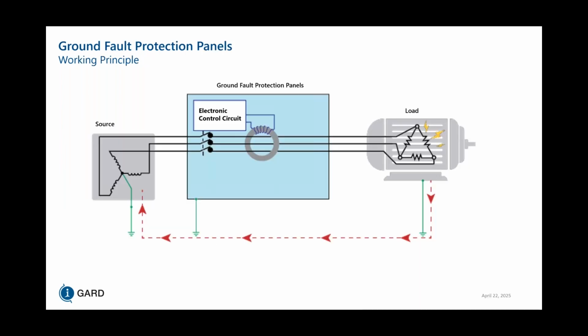In a typical ground fault protection panel, it comes with a means to break the circuit, via a circuit breaker or a contactor, and it uses a ground fault relay with a CT that's wrapped around the three-phase conductors and/or the neutral to pick up any ground fault downstream of the CT's location. That way, when the load is experiencing a ground fault, that ground fault current will circulate back and be seen by the CT, which is then processed by the relay, and the relay sends a trip command to open this breaker to stop the equipment from running for safety purposes, for both equipment as well as personnel that could be in close proximity to the equipment.